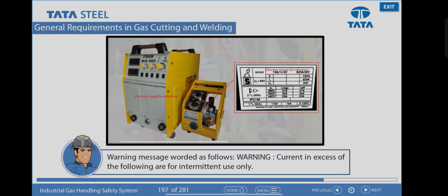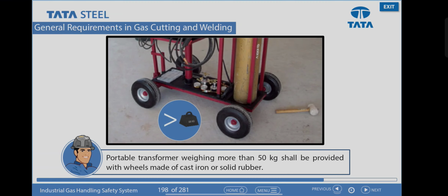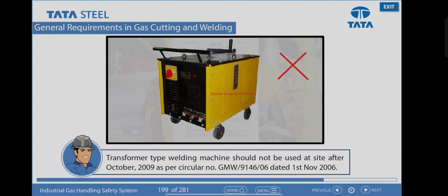Warning message worded as follows. Warning. Current in excess of the following are for intermittent use only. Portable transformer weighing more than 50 kilograms shall be provided with wheels made of cast iron or solid rubber. Transformer type welding machine should not be used at site after October 2009 as per circular number dated November 1st, 2006.